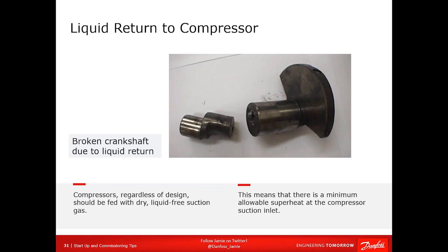Okay, we've talked lots about high suction temperatures and setting things on fire, burning them up, whatever. Well, the opposite side isn't much better. You want your superheat to be low enough to keep the compressor cool, but you don't want it so low that if you get a sudden load increase on the evaporator, something happens, liquid's going to come flooding back to the compressor. All right, so you need to have a minimum level of saturated suction superheat. Now that sounds like an oxymoron, but saturated suction just refers to the saturation temperature of the refrigerant at the compressor inlet. It is not going to be the same as at the evaporator.